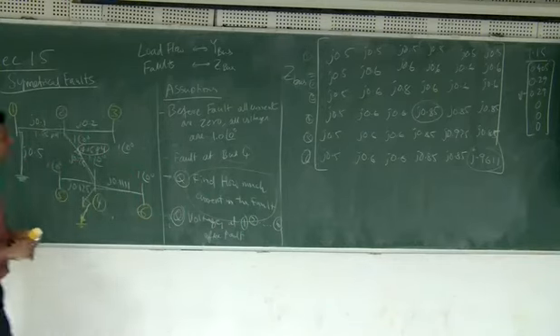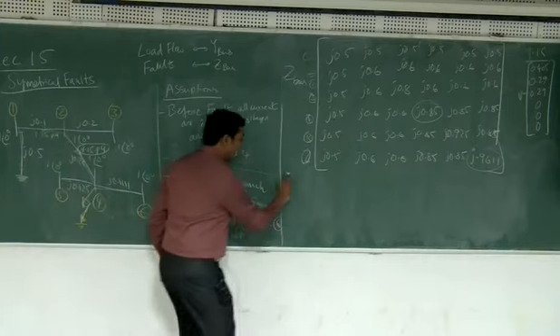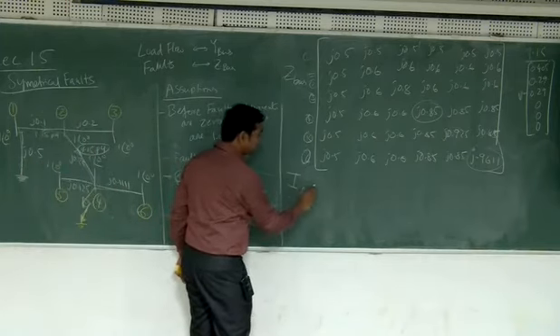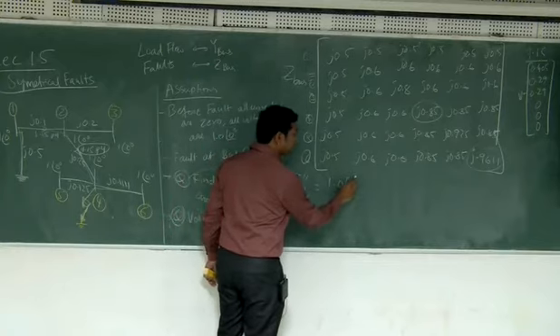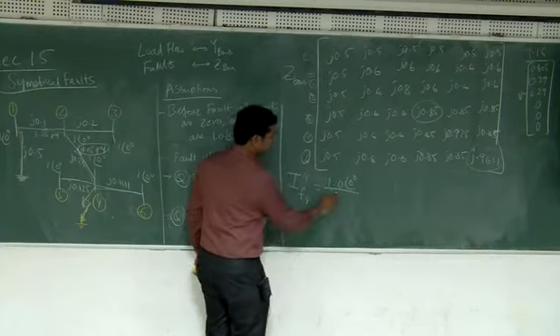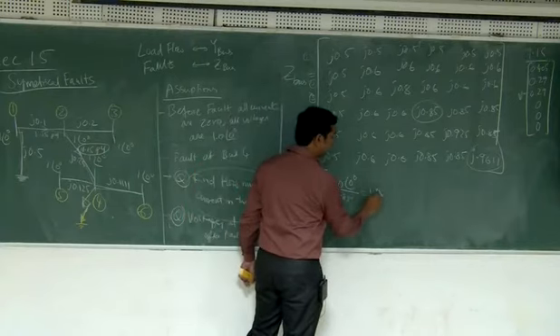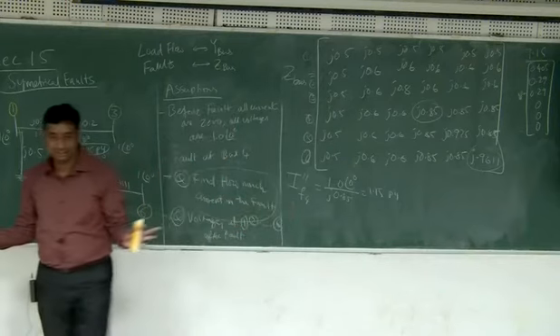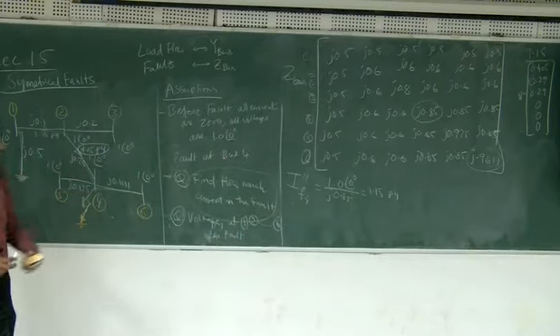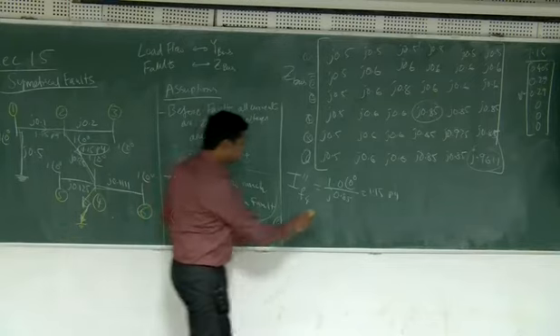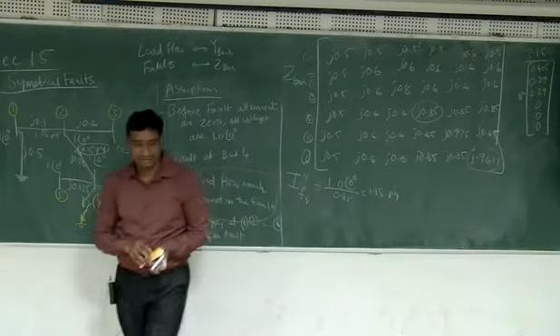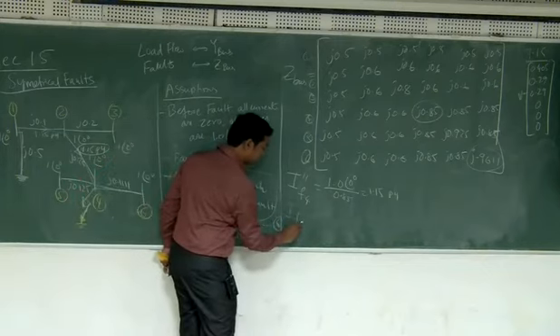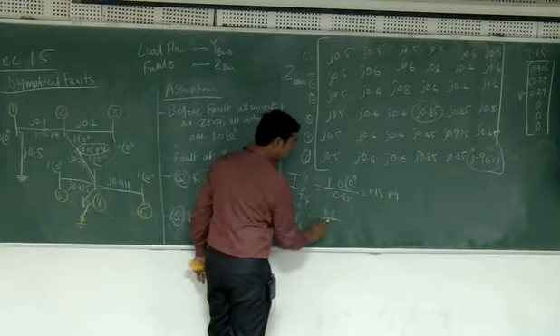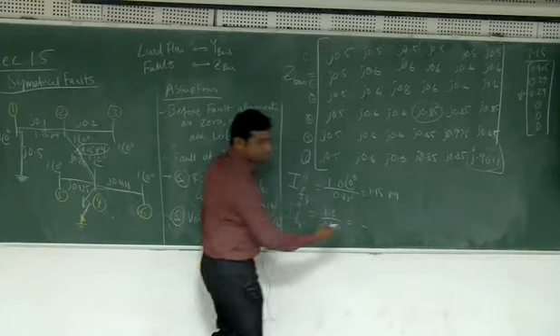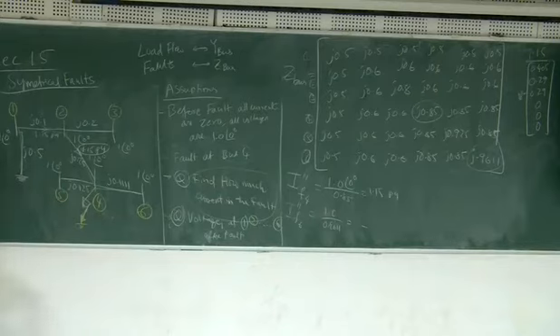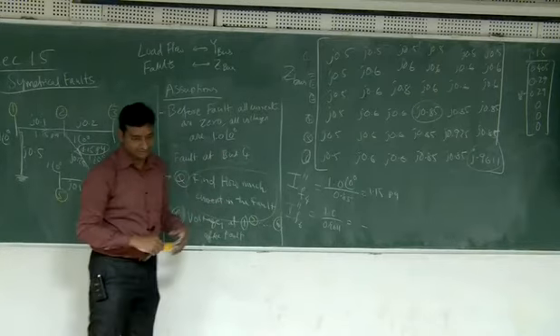Okay. So now if I want to calculate fault current at bus 4, IF4 double dash is equal to 1.00 degrees divided by J0.85, that will be 1.15 per unit. So this was my calculation. I think some J should be there, but we are just worried about the magnitude now. So this is my fault current. Fault current at bus 6 will be 1.0 divided by 0.9611, so some number will come. So if you calculate your Z bus once, then fault calculations become faster.